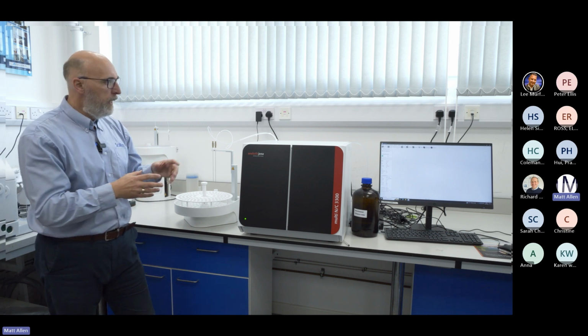So we have this system called the Vita gas flow measurement, which is basically a number of mass flow controllers and mass flow meters within the system that are constantly measuring gas flows, and they can correct and regulate and normalize for this change of pressure. So it means that we can be very, very sure and very confident in the reproducibility and our accuracy of our results from one sample matrix to another, from one calibration curve to another.